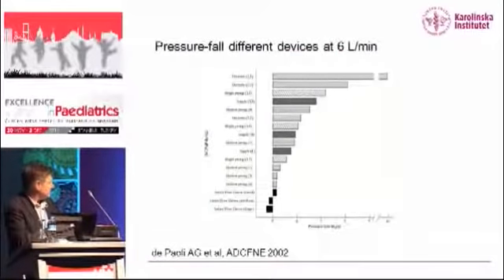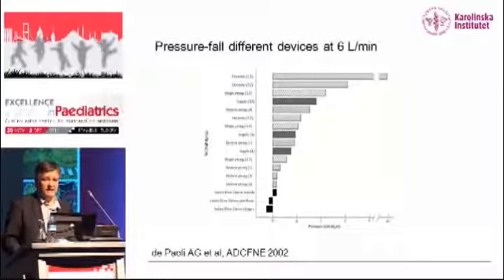The nasal attachment is, of course, very important because the resistance in the nasal attachment, whether it be prongs or a tube or anything, is very important. You see, this is the resistance here, and this is the pressure. And these are tracheal tubes, and you see there's a lot of resistance here. And as you go down, here's the Argyle, which many people use, and here is the Hudson prong, and here are the infant flow devices. So resistance is obviously very important relating to the device that you are using. If you use a bad attachment with high resistance, you'll get very bad results.